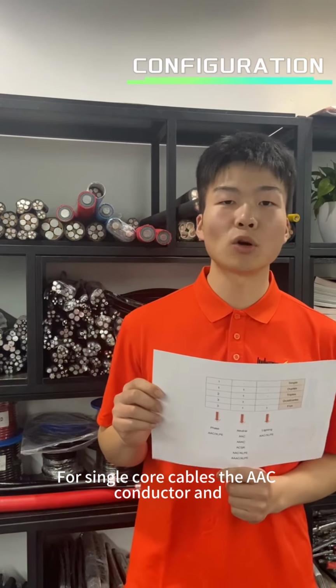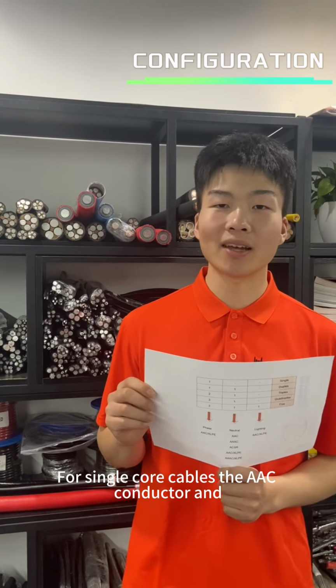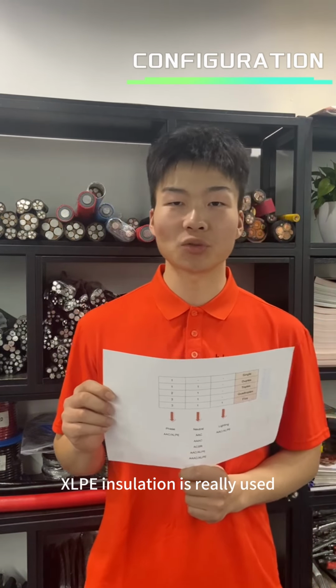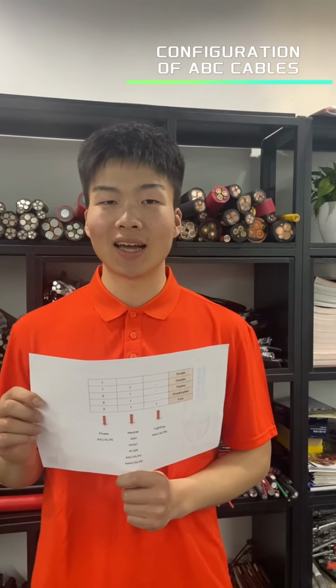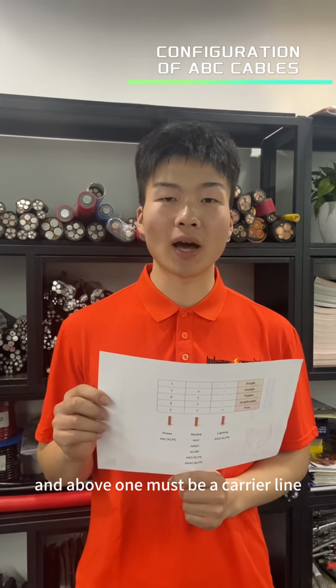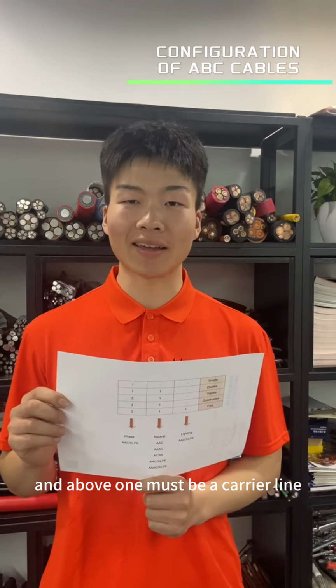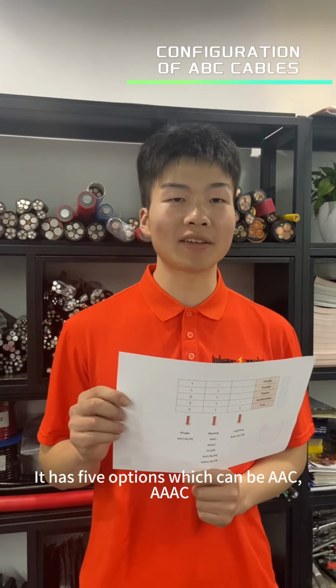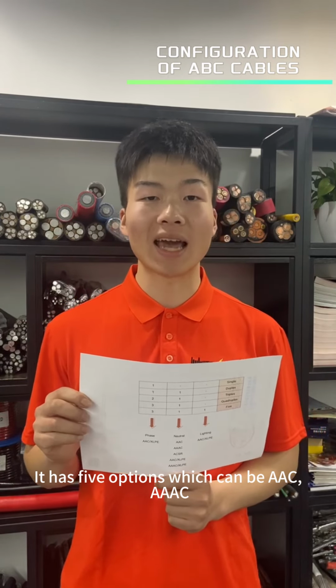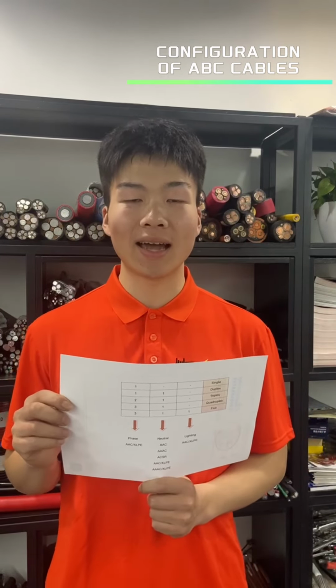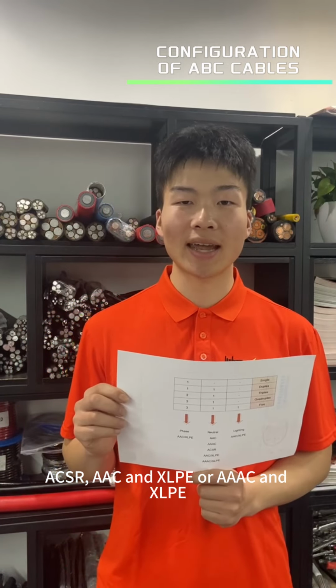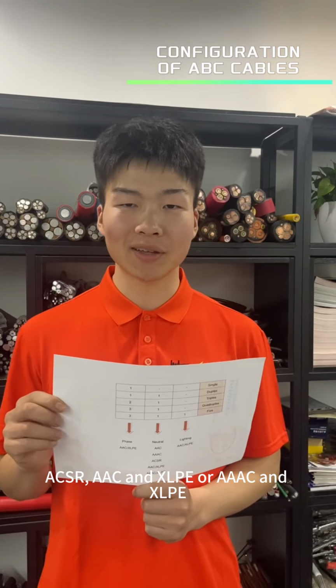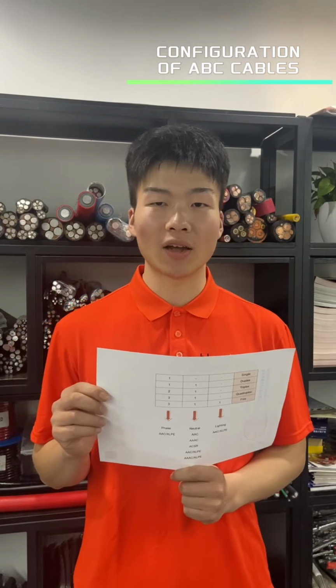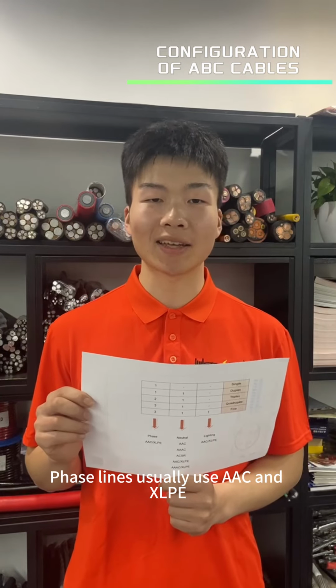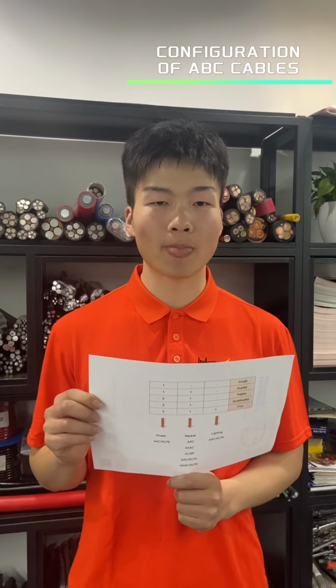For single-core cables, the AAC conductor and XLP insulation is rarely used. In twisted pair cables and above, one must be the neutral line, which has 5 options, which can be AAC, AAAC, ACSR, AAC and XLP, or AAAC and XLP. Phase lines usually use AAC and XLP.